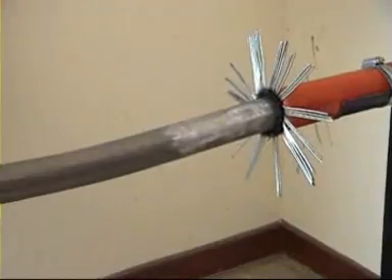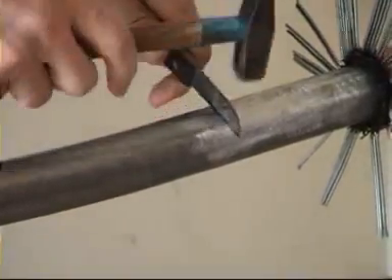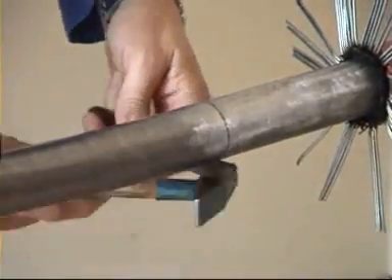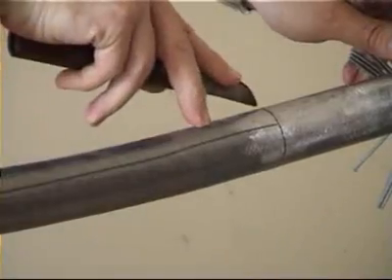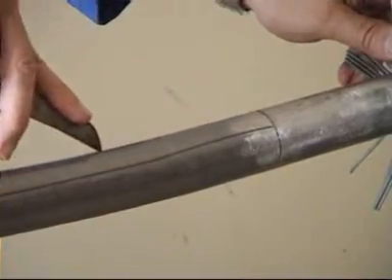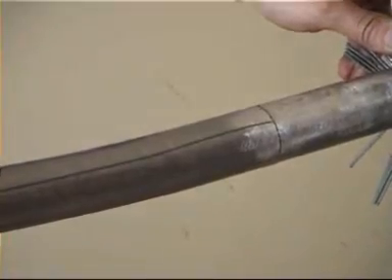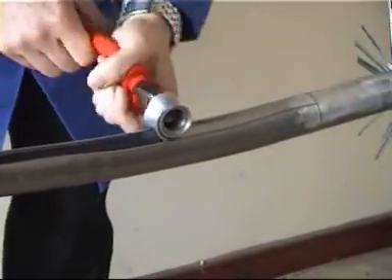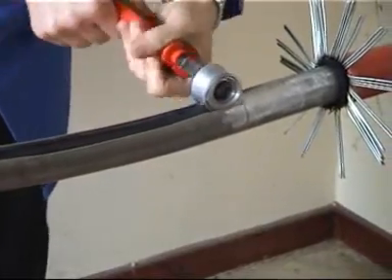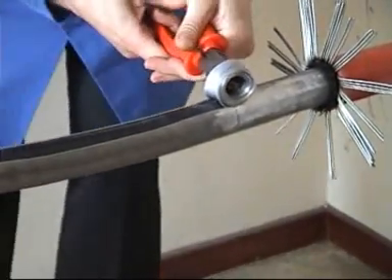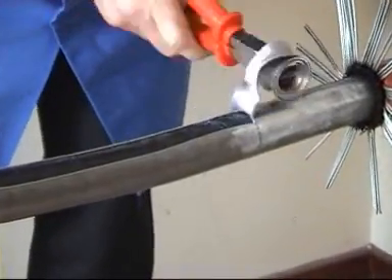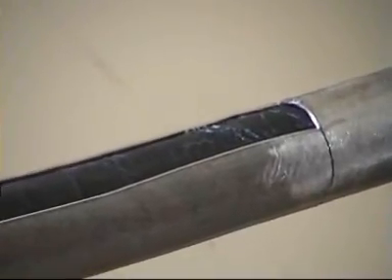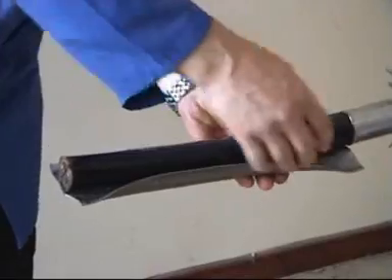Mark the lead sheath cut and with a sharp knife make a circumferential cut on the lead. Score the lead longitudinally and peel off a strip of lead as shown.